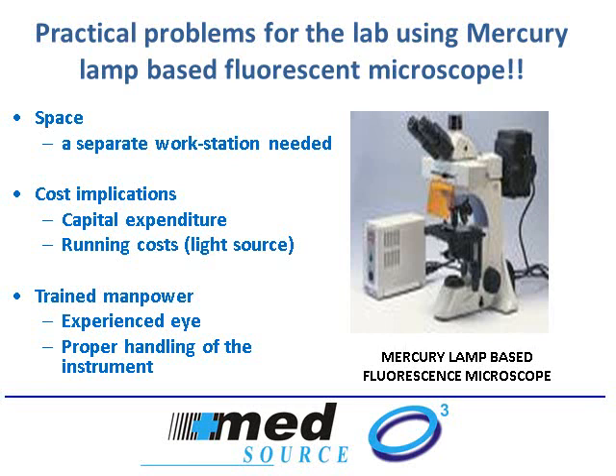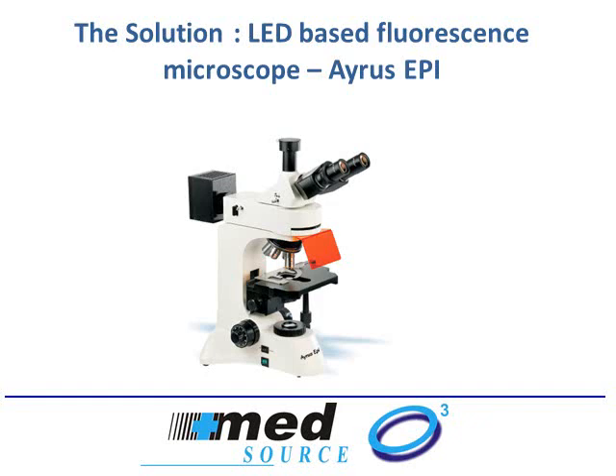Most of these problems are now addressed with the LED based fluorescent microscope Ayrus EPI. So Ayrus EPI is our new microscope which is for fluorescence and it uses LED as a light source. That means we don't have any mercury lamps and the mercury lamp is replaced with LEDs. LEDs are light emitting diodes which have a long life and many advantages that we will cover in the upcoming slides.